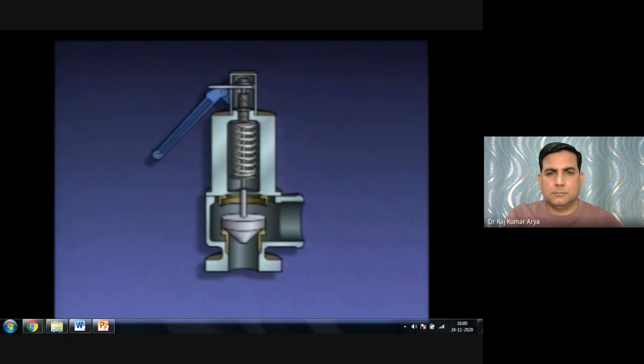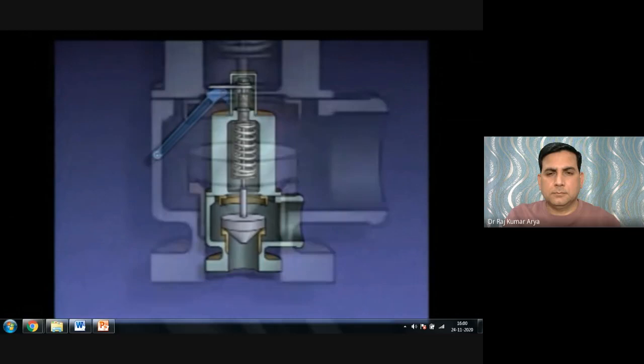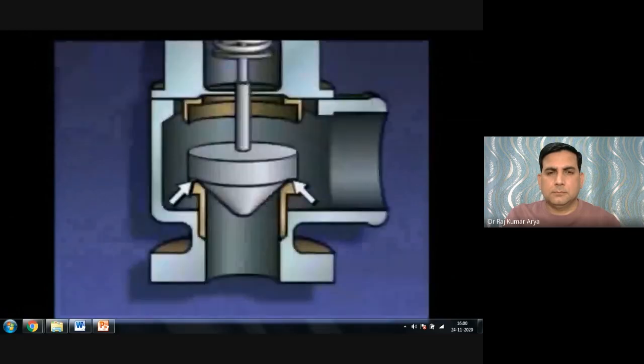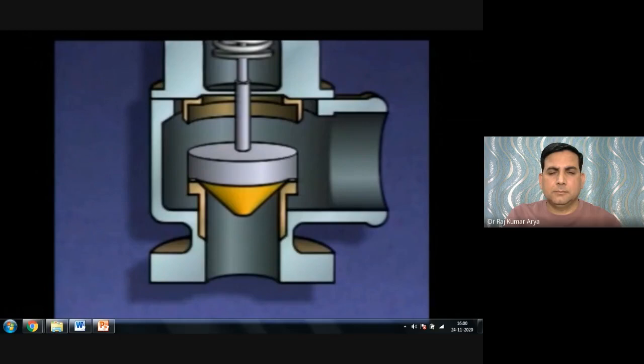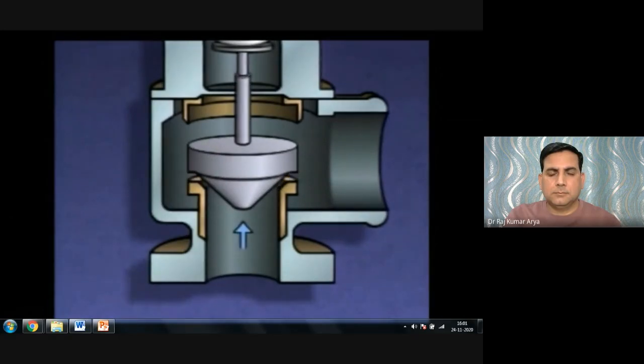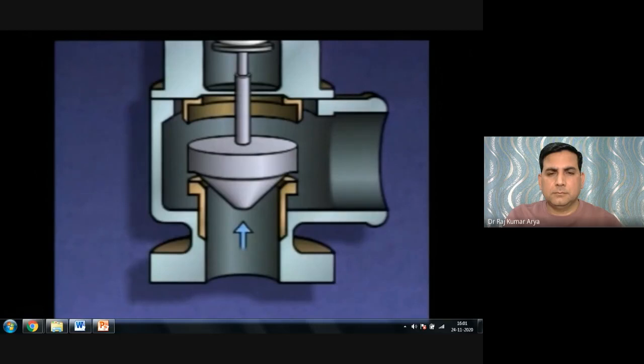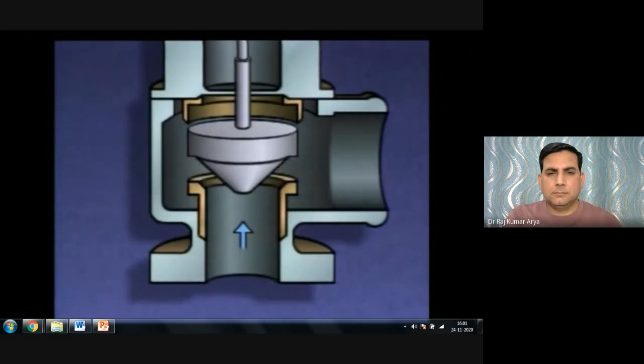The disc of a safety valve has a lip that is not exposed to system pressure when the valve is closed; only the center portion is always exposed. When pressure reaches the preset lift value of, say, 200 psi, the disc starts to lift and the lip of the disc is suddenly exposed to system pressure as well. Since a larger area of the disc is now exposed, more force is exerted on the bottom of the disc, causing the disc to pop open to about a 60% open position, allowing a large volume of fluid or gas to escape rapidly.